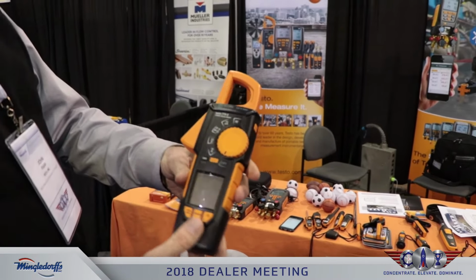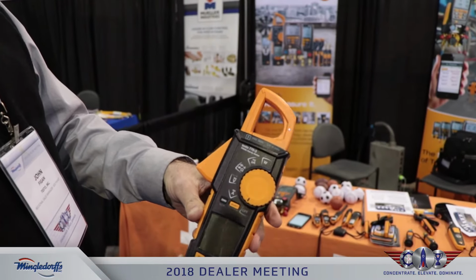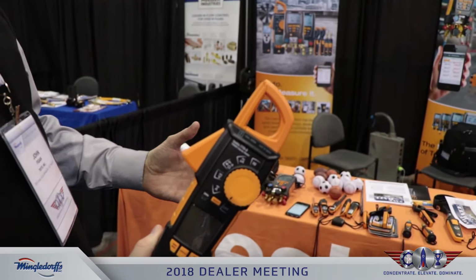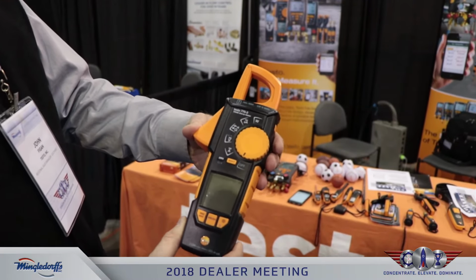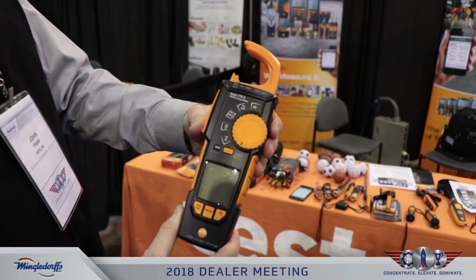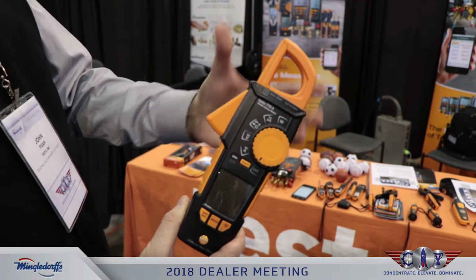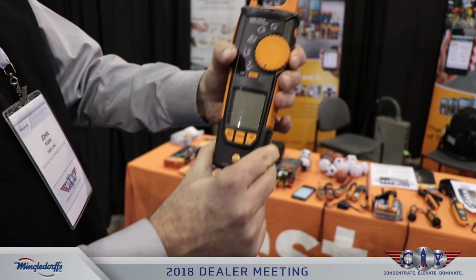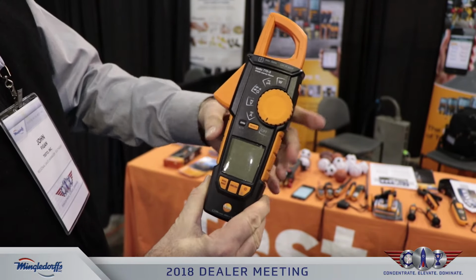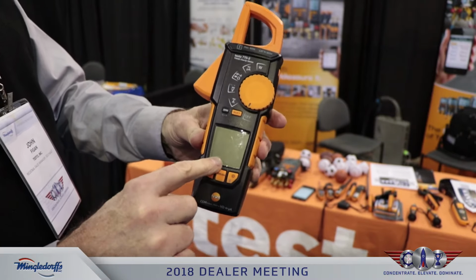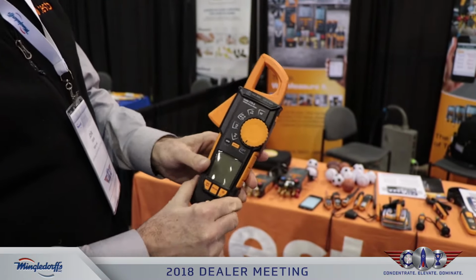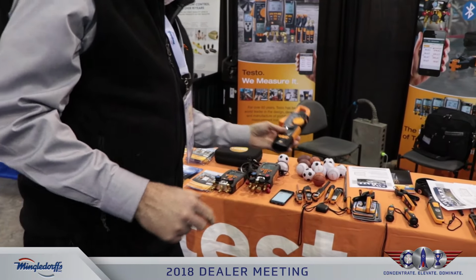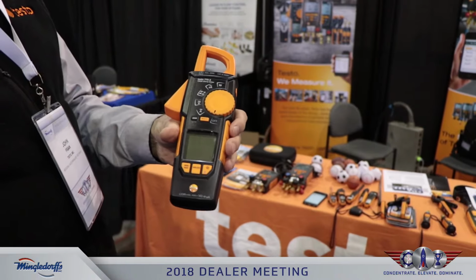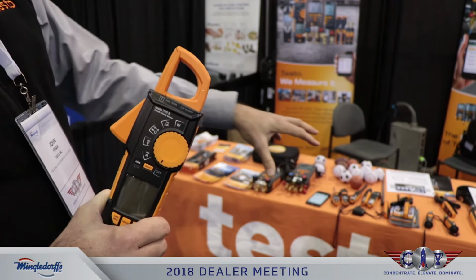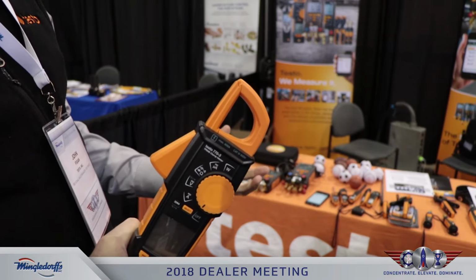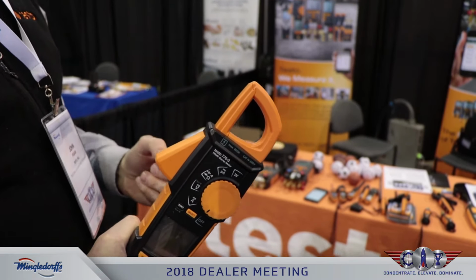The other line of instrumentation is really the electrical line of instrumentation. We have a multimeter, we have a voltage indicator, we also have a unique clamp meter, and you can see how that plunger goes down instead of opening up like a clamshell. And the reason why we do that is you can grab the wire, isolate the wires, put it in there, and get your amps. This also has Bluetooth capability, so it also is combined with these instruments over here. We can look at amps, we can look at voltage on the app, and start making calculations like SEER calculations or power calculations, things of that nature.